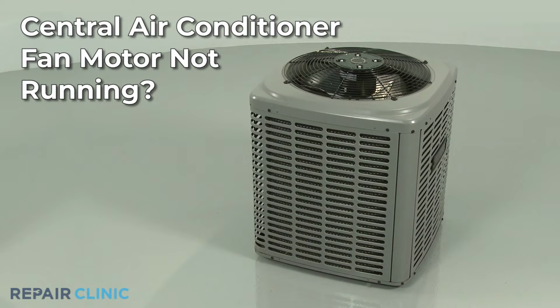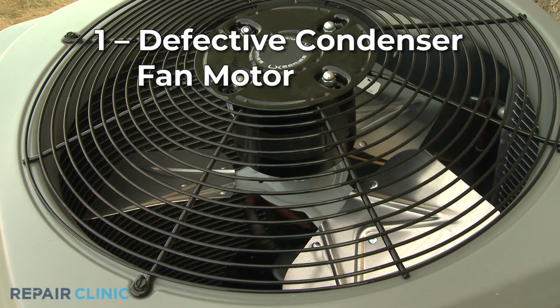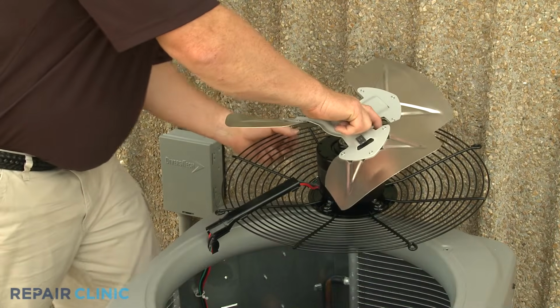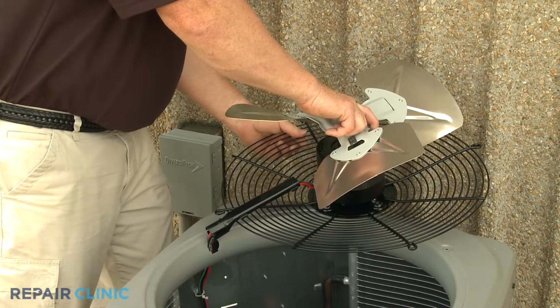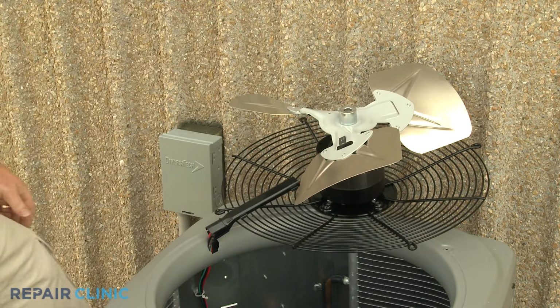If your central air conditioner fan motor is not running, here are the two most probable causes. The condenser fan motor itself could be defective. The fan blades attached to the motor shaft should rotate freely. If they do not, it's likely the motor has seized.